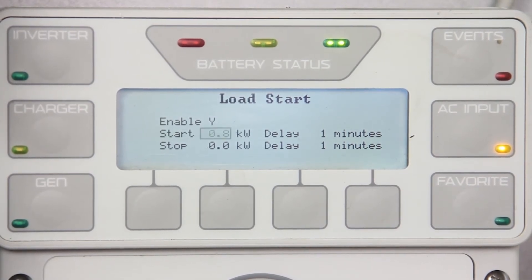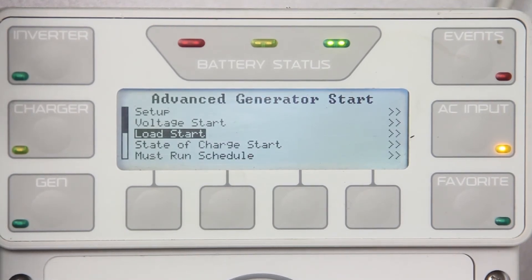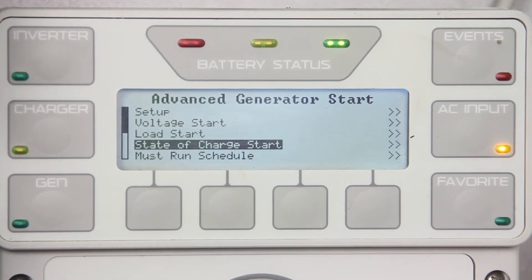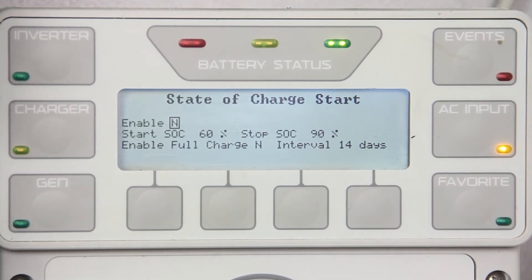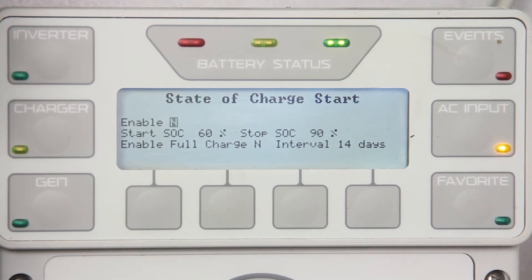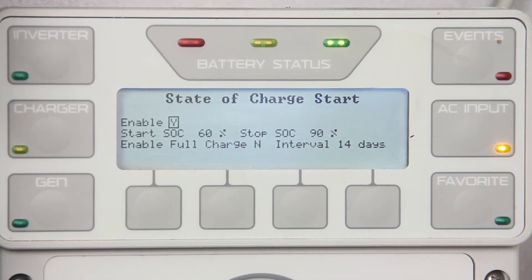Press up once and scroll down to state of charge start. With the FlexNet DC you may start and stop the generator based on its percentage state of charge and an optional enable full charge every interval time. To enable, change the N to Y and enter the desired start/stop conditions.